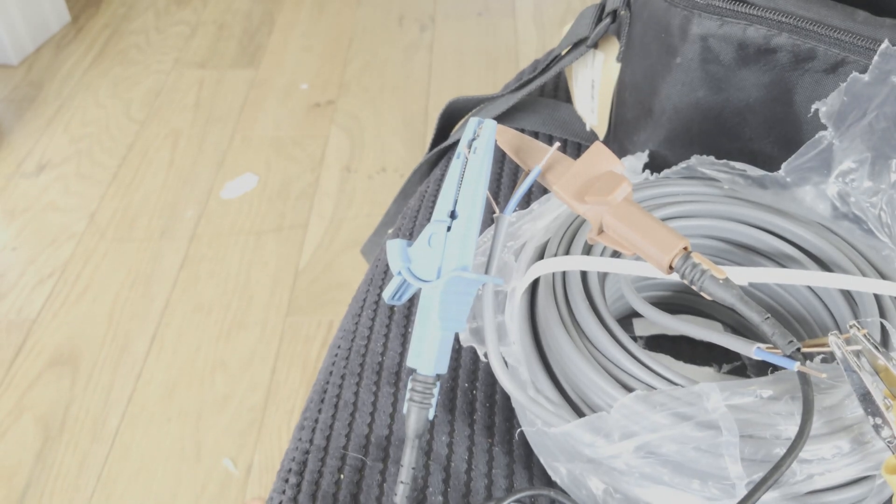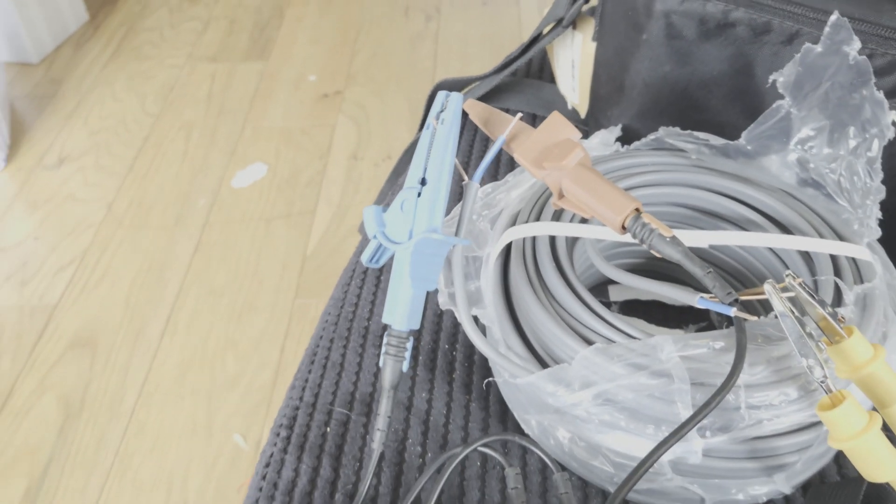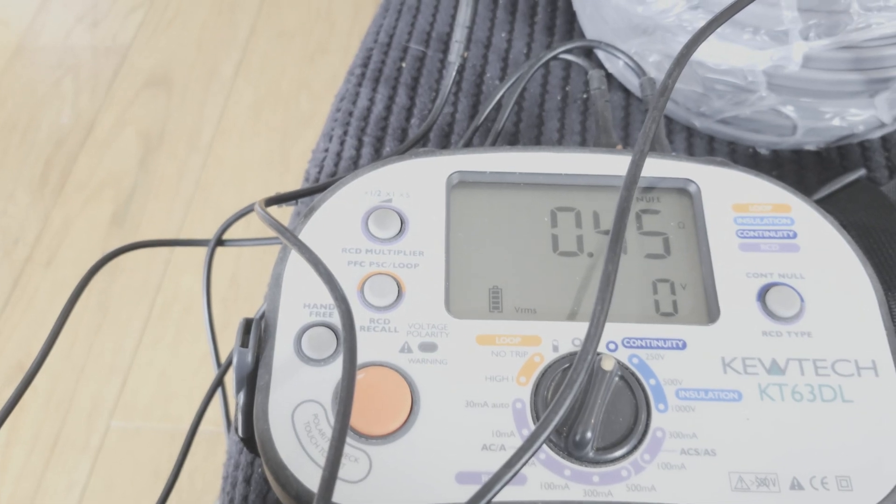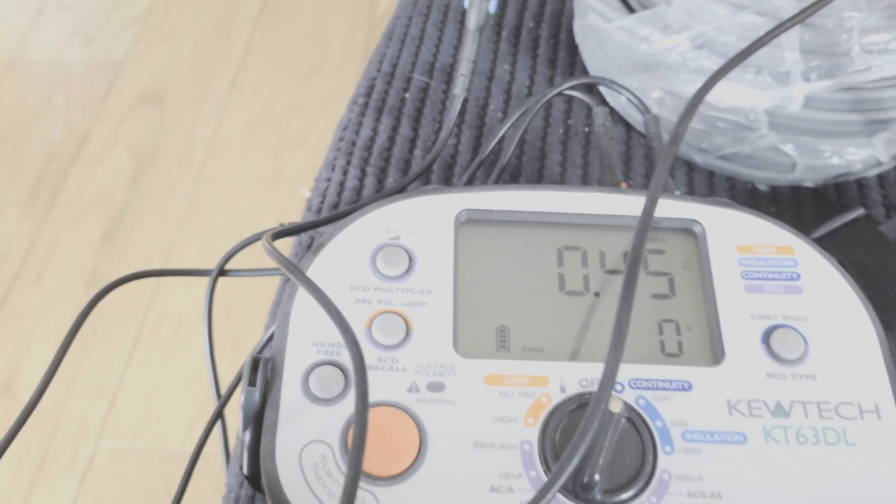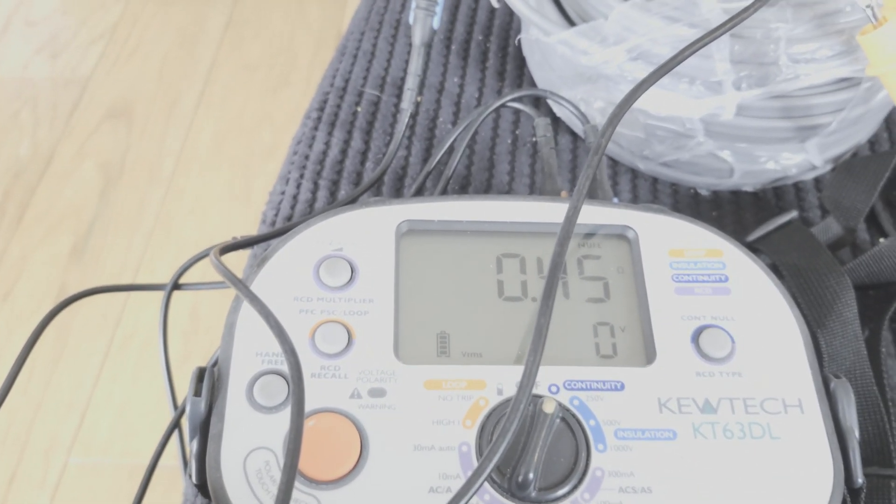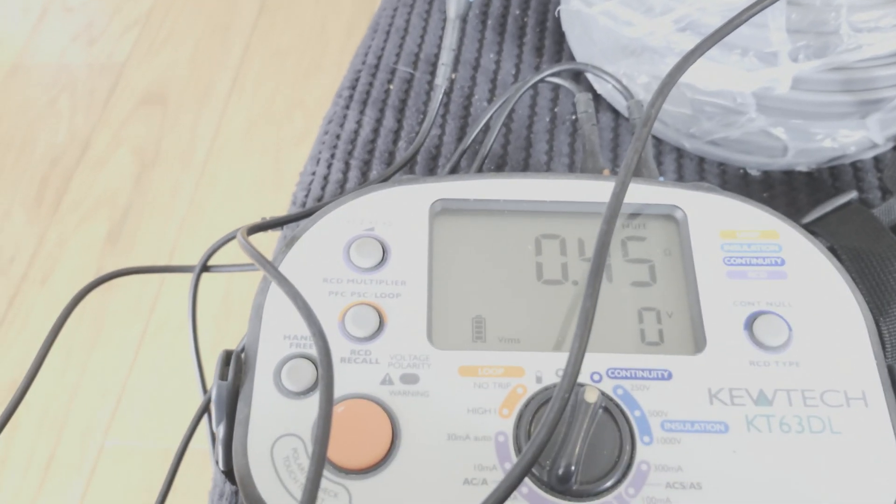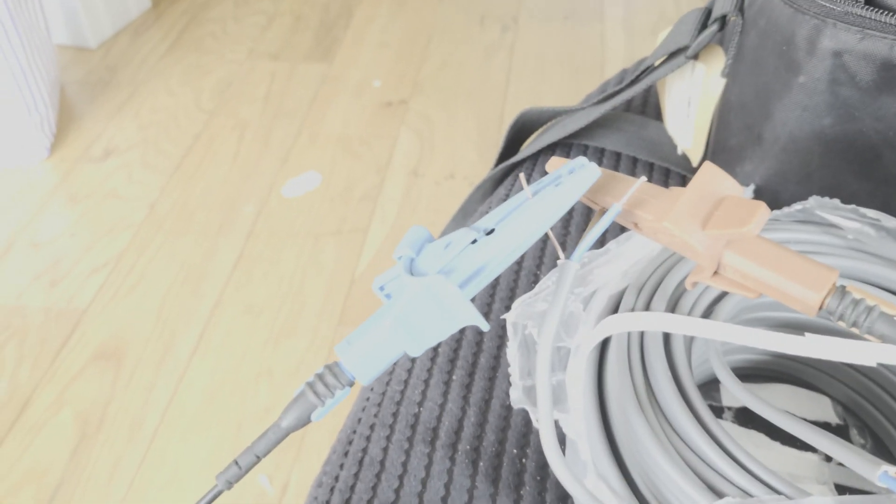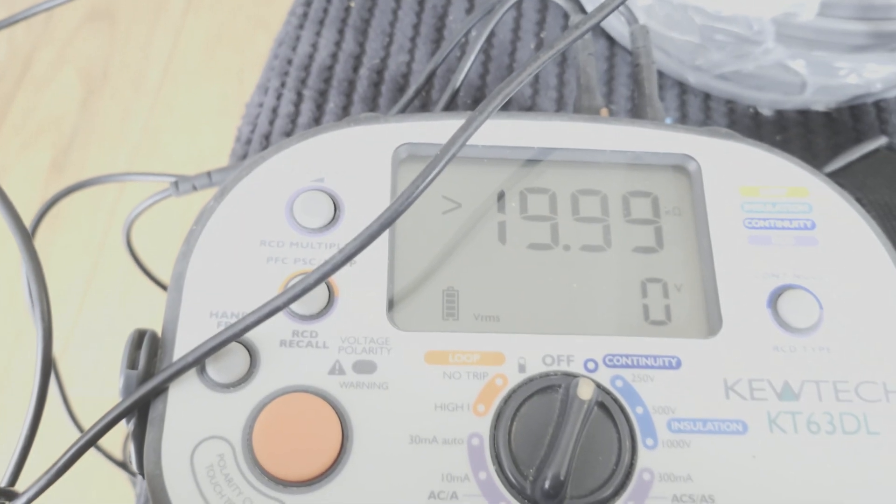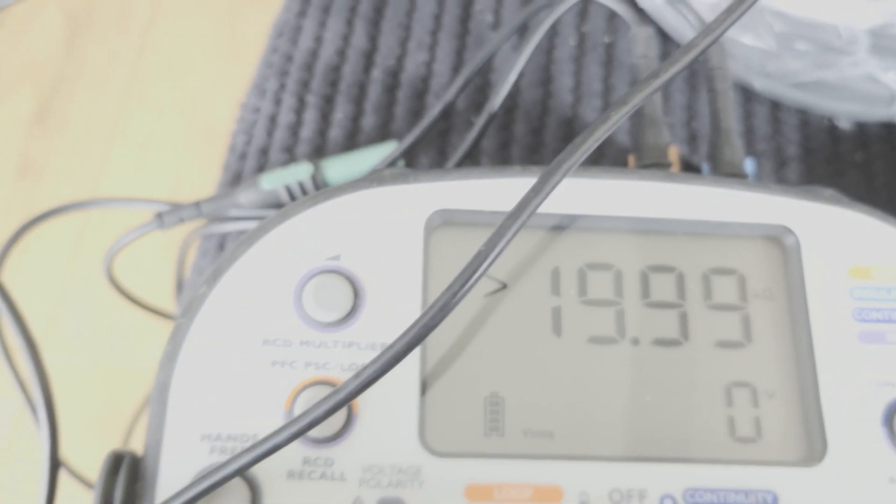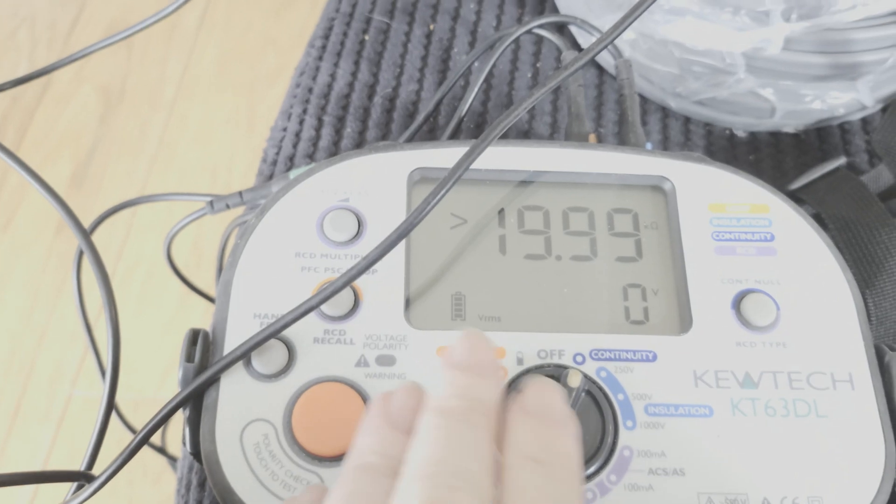That just proves that what I've done actually gives me the right reading. What would happen if I try to do that without nulling those cables? Let's have a look. These cables are still connected, but now as you can see there's no null in the screen. So if I now press the test button, that's the reading I get, which is totally wrong.